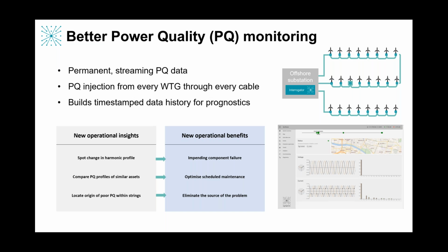In a nutshell, what we're saying is you can spot a change in the harmonic profile from a turbine, which tells you of an impending component failure. That could be a converter or a filter or a bearing. You can compare like for like assets and say, why are these other 40 turbines behaving the same and have one signature and then the 50th one doesn't? That means you know to go and visit that one because something's about to go wrong, and that means you optimize your scheduled maintenance regime, and that's going to improve costs and anticipate failures with reduced outage.